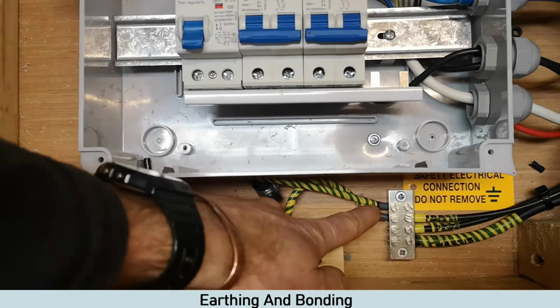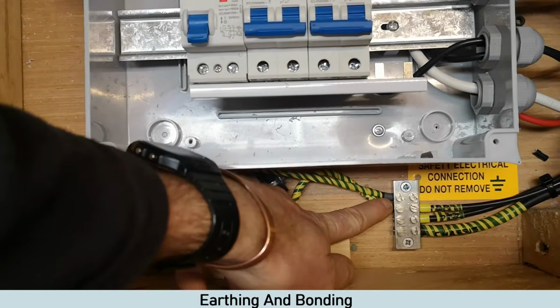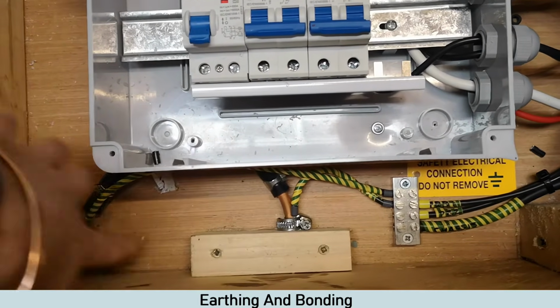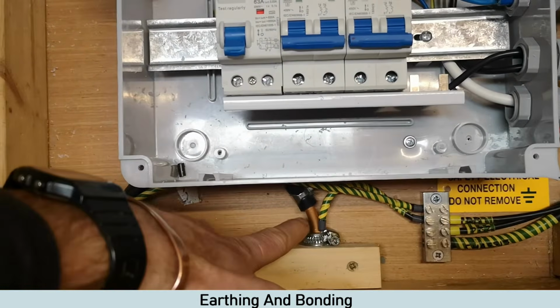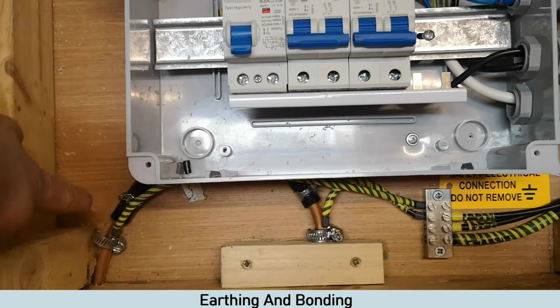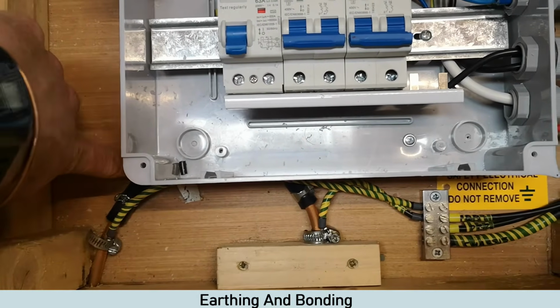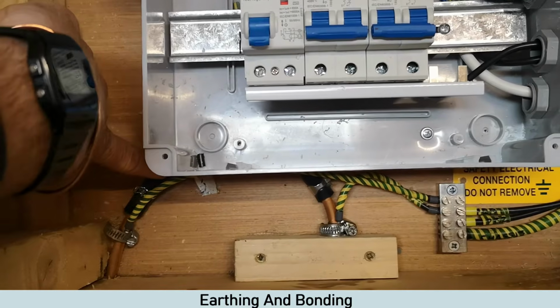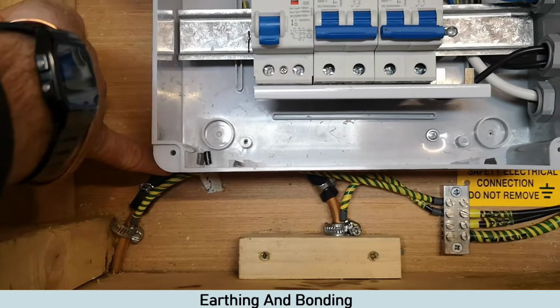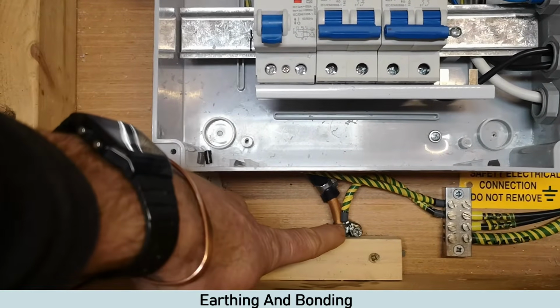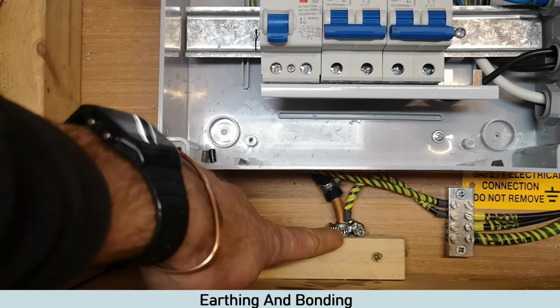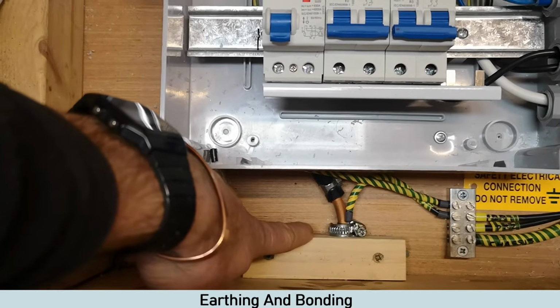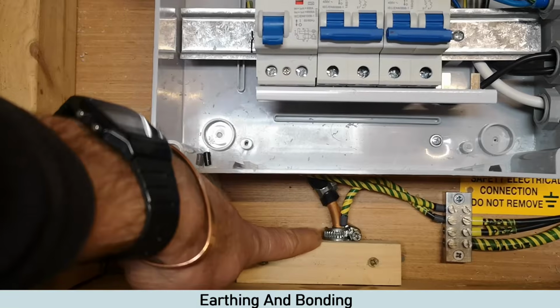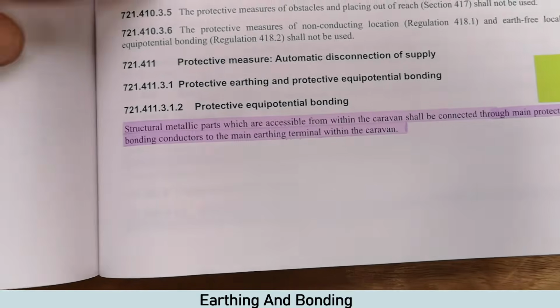So the other two we have are bonding conductors. These run to these pipes here. These are our underfloor heating pipes, and the reason we've got two bonds is because there's a rubber pipe here, and where they run into our cupboard they're not joined, so we've just joined them there. We've got a bonding cable to our gas pipe as well, because that runs through a cupboard with electrics in. So again, I'll show you the regs.